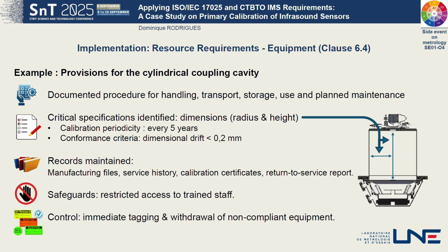The cost to repeat unnecessary control of this calibration, and the risk that, in fact, the dimensional drift exceeds the conformance criteria that we choose. So it's a balance between these two things, and here in this case we choose 5 years, which is enough because the cavity is in steel, and the conformance criteria is quite large for this device.